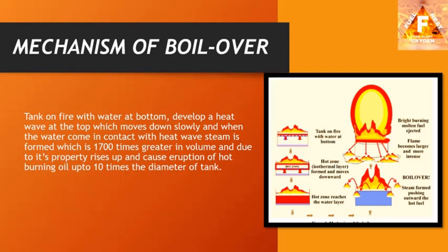Here you have a schematic diagram of the different stages of a boil over phenomenon. First, the tank is on fire and there is water below the fuel area. Then the hot zone or heat layer is formed and moves downwards towards the water. The hot zone reaches the water layer and then the boil over occurs — steam formed pushing outward the hot fuel — and later this results in bright burning molten fuel as the heat layer is ejected and the flame becomes larger and more intense.